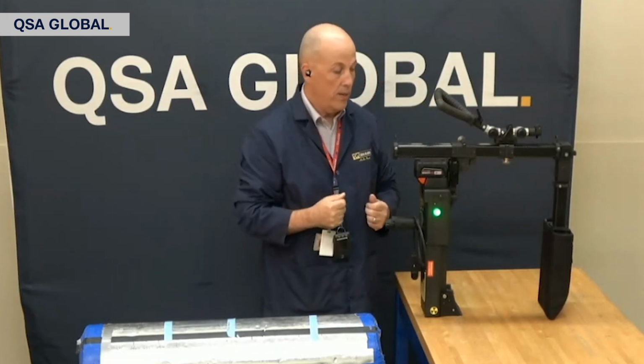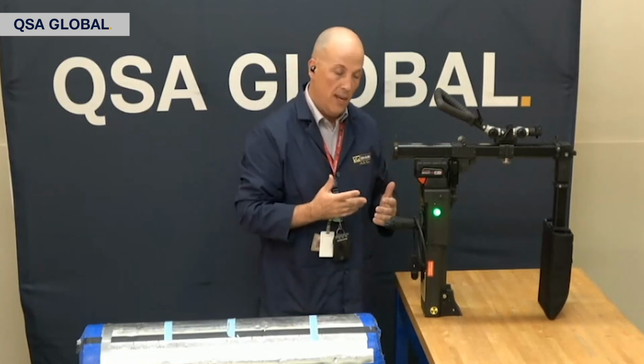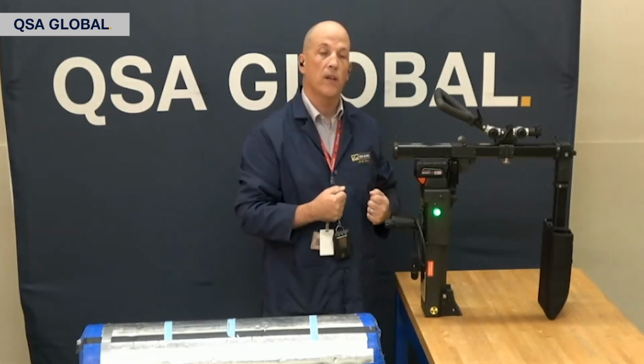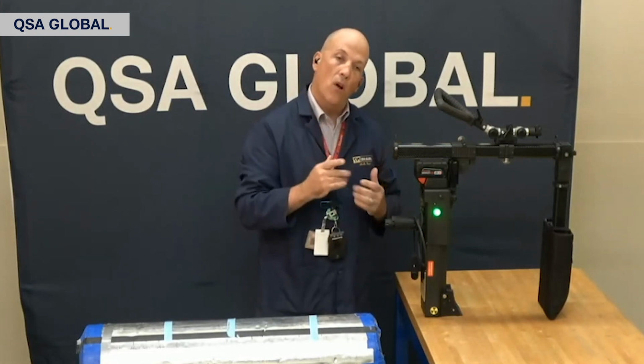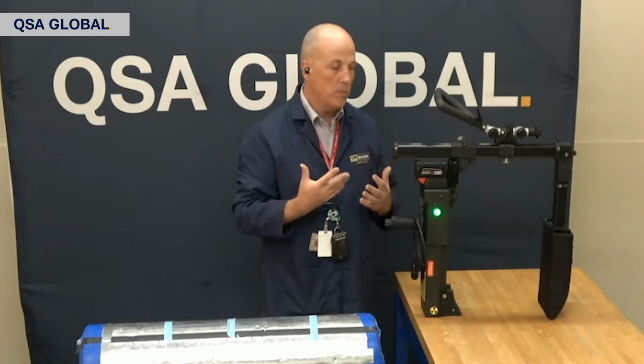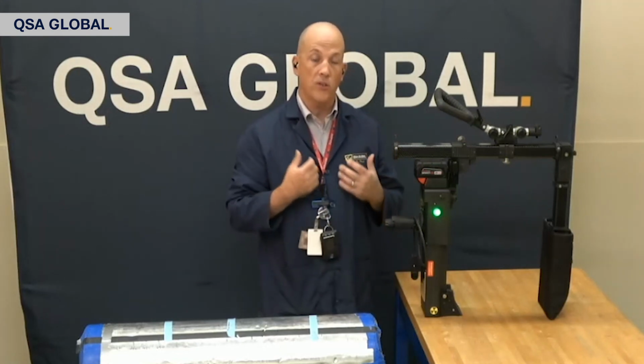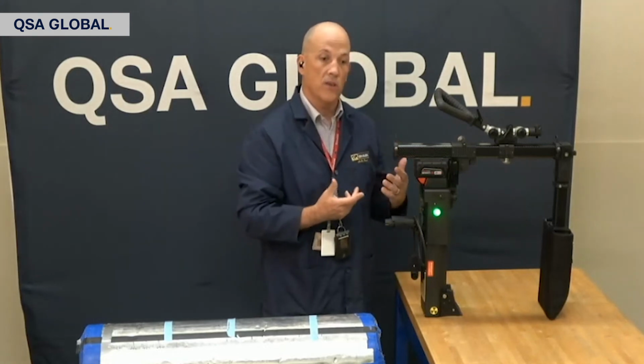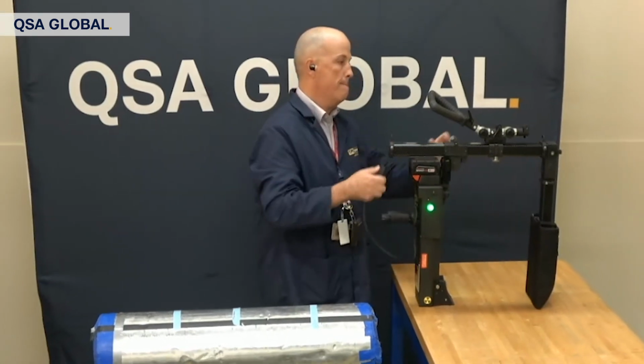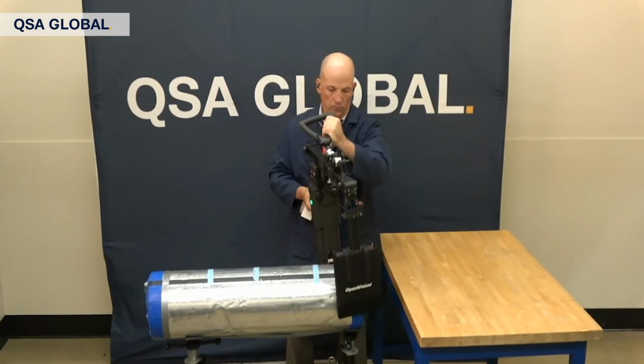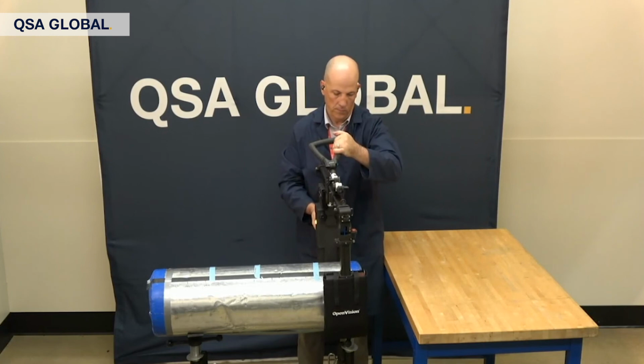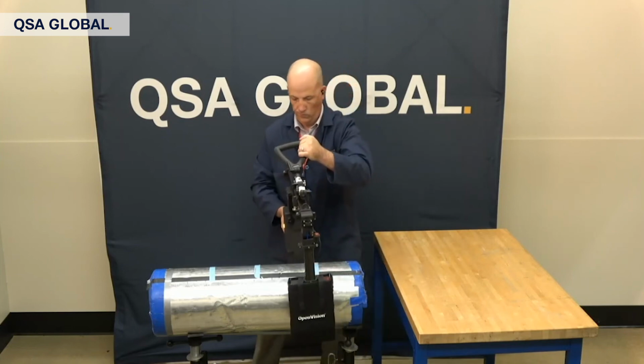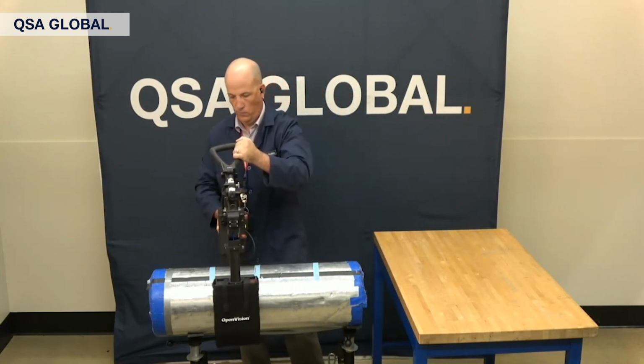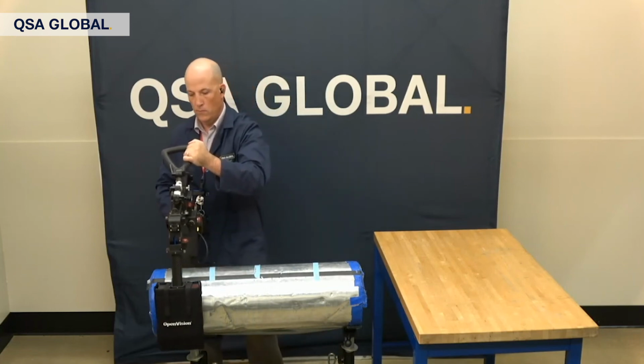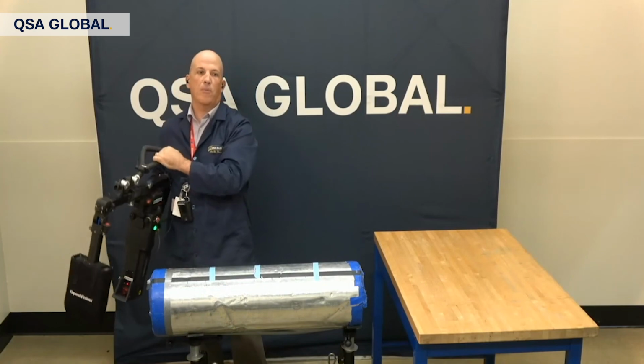Now you're ready to initiate X-rays. To perform the real-time radiography scanning, I'm going to initiate the trigger. It's going to give you a 5-second warning, and you're also going to see the amber light turn on. So you have multiple methods of letting you know when our X-ray is going to be engaged. Once the X-rays are engaged, you can begin your scan, and you're performing real-time radiography.